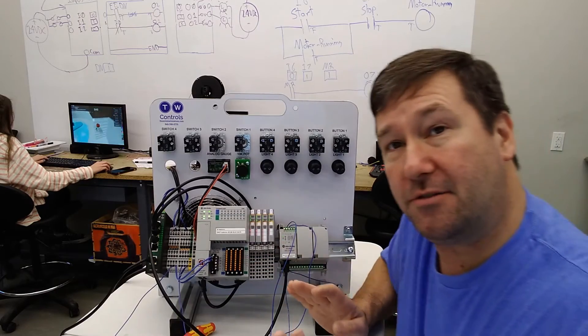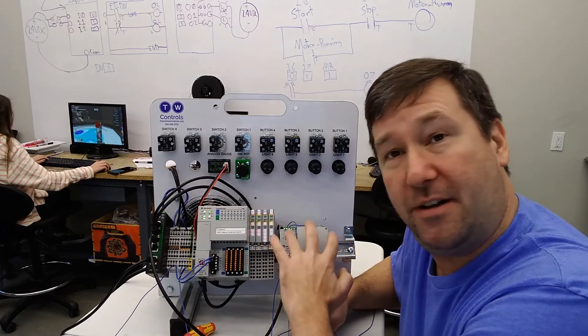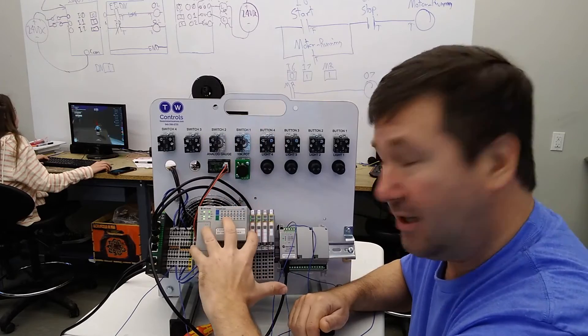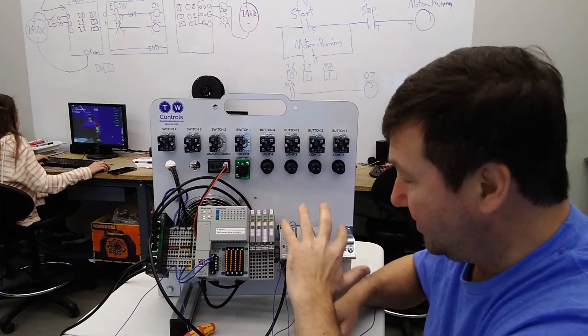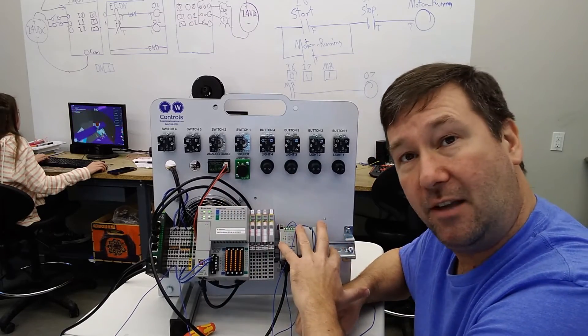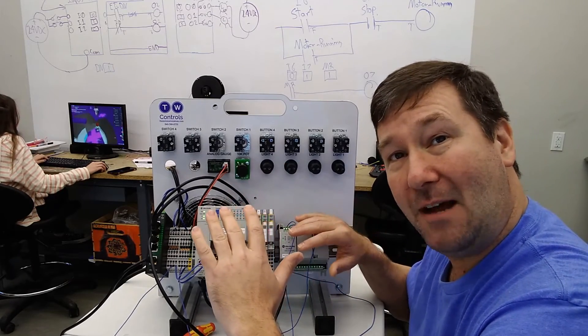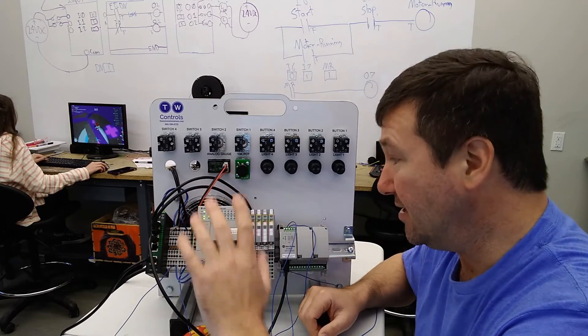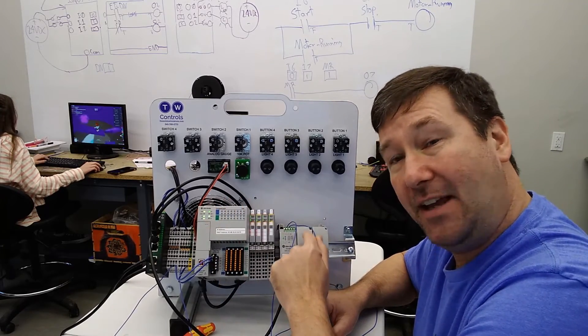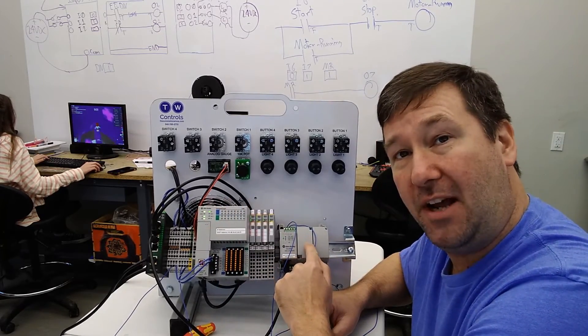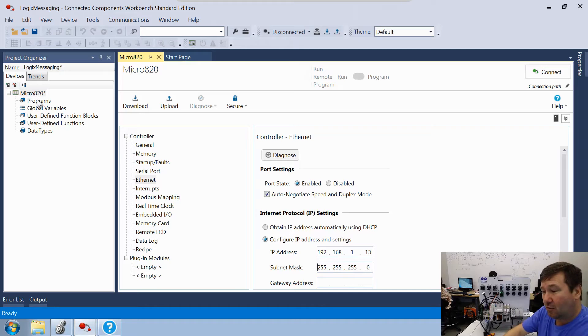Let's make sure we understand this, because this is the first time we've deviated from our standard IP address in these lessons. Both our ControlLogix/CompactLogix Studio 5000 lessons and our Micro 800 Connected Components Workbench lessons use the same default IP of 192.168.1.10 — which is what we've kept the CompactLogix at. So this Micro 820 needs a different unique IP address to communicate, and I've chosen .13 for it.